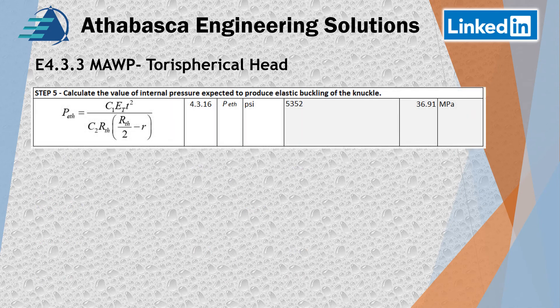Now we're getting some actual useful information. We needed C1 and C2 to put our values into this step. Here's where we use values like the modulus of elasticity. We calculated R_th earlier — this is step 4.3.6 — and then we calculate the pressure to buckle the knuckle, which is really, really high. It's amazingly strong, and this buckling calculation is only available in Division 2.